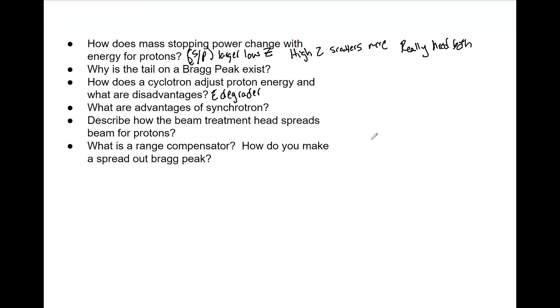Now, what are the advantages of a synchrotron? You get a proton from a linac. It accelerates through RF cavities that match the frequency of the protons, and because the magnetic field is varied, they stay in the same rotation and can make beams of precise energy. They don't need degraders—that's really the big thing. While cyclotrons can work and give you precise beams, they have those negative attributes. Synchrotrons don't need those degraders, so there's less shielding, you don't have to worry about neutrons, and you don't have the post-treatment radioactivity.